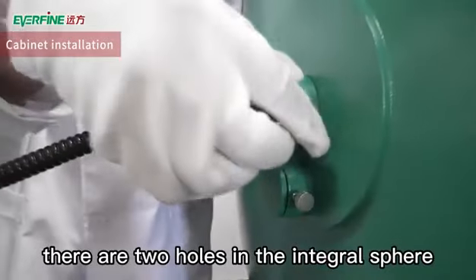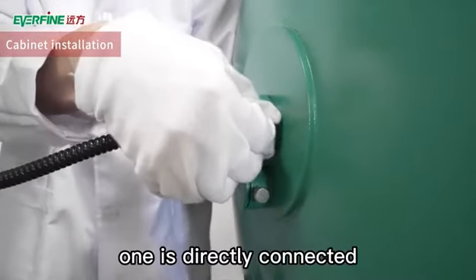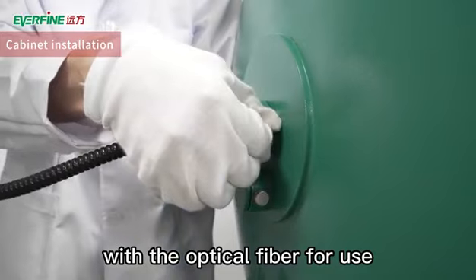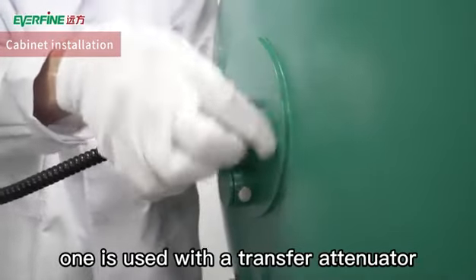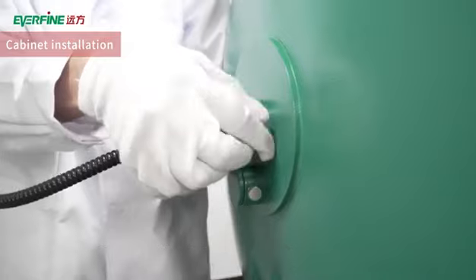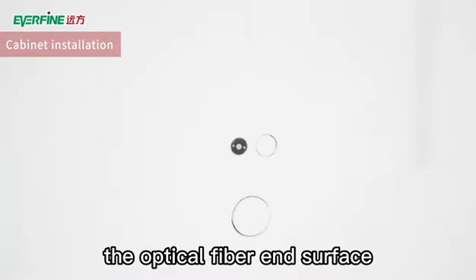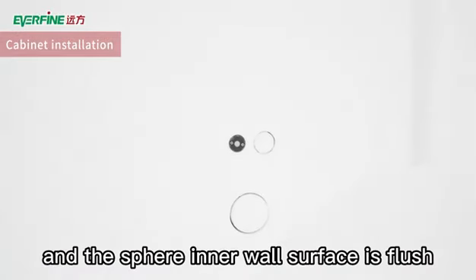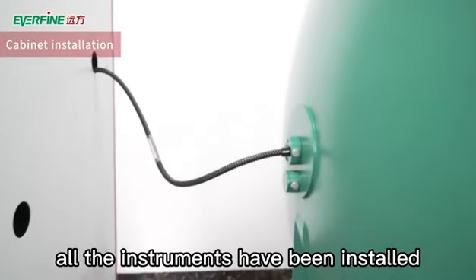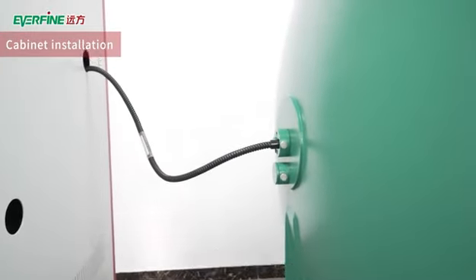There are two holes in the integrating sphere. One is for direct connection with the optical fiber. The other is used with a transfer attenuator. The optical fiber end surface and the sphere inner wall surface should be flush. All the instruments have now been installed and secured.